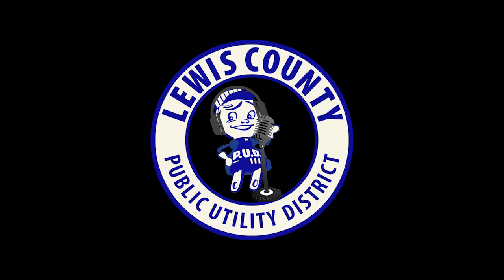With solar, when it first came out it was a big topic, and now utilities are pretty comfortable with it, mainly because people were putting in systems willy-nilly back in the day. Now all the inverters have a safety feature built in as part of the application process. Engineering checks for IEEE 1547 or UL 1741 certification on the device, which guarantees it's been through a lot of testing and has a rapid shutdown feature—if it loses connection to our system, it shuts down so it doesn't backfeed. If a customer has batteries, the inverter takes that into account, disconnecting from us but supplying power to their house from the batteries. There are safety features embedded into all of that.